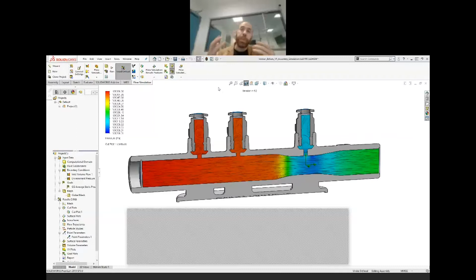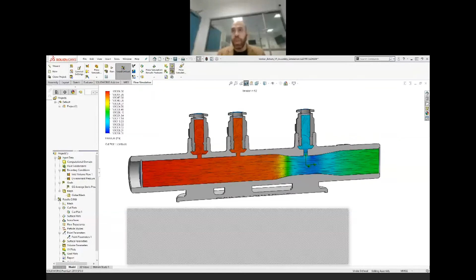We were adamant to have a redundant system where we have two sets of measurements on the inlet and on the outlet to be able to measure how much we're giving. So we measure the pressure, we measure the flow. This is extremely important to make sure that we are giving and delivering exactly what is required. I think in a nutshell, this is how it works. I'll leave the floor to Dr. Ali. We'll go over probably the 3D model, the whole design, how it is done, and then we can continue.